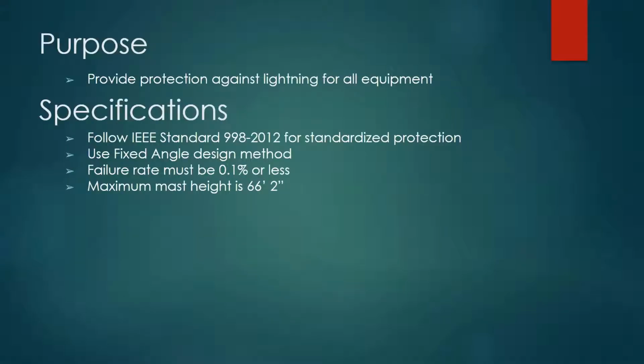So the purpose of the design was to protect all equipment against any lightning strokes that would be in the area. We had some specifications we had to follow. First, we had to follow the IEEE standard for lightning protection. We were required to use the fixed angle design method, as our sponsors were most familiar with this method. The failure rate must be 0.1% or less, and the maximum mast height was to be 66 feet and 2 inches.